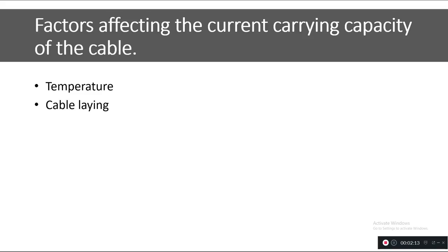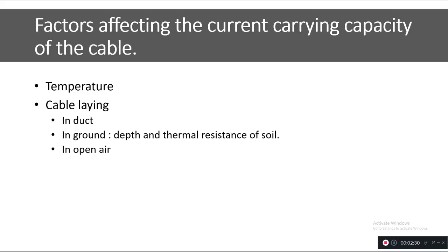Next is cable laying. It depends upon how you are laying the cable — whether in open air, underground, or in a duct — because that affects the current carrying capacity. Whenever you consider laying the cable underground, you also need to consider the depth at which the cable will be laid, as well as the thermal resistivity of the soil, because that will affect the current carrying capacity of the cable.